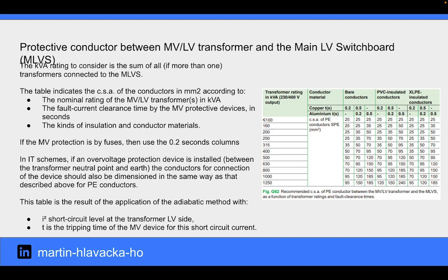The table indicates the CSA of the conductors in millimeters squared according to the nominal rating of the MV-LV transformers in kVA, the fault current clearance time by the MV protective devices in seconds, and the kinds of insulation and conductor materials. If the MV protection is by fuses, then use the 0.2 second columns. In IT schemes, if an overvoltage protection device is installed, the conductors for connection of the device should also be dimensioned in the same way as described above for PE conductors.